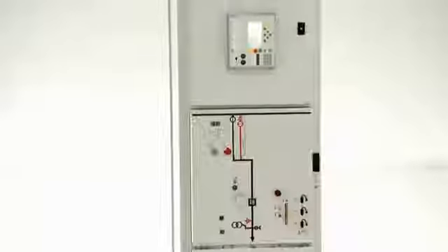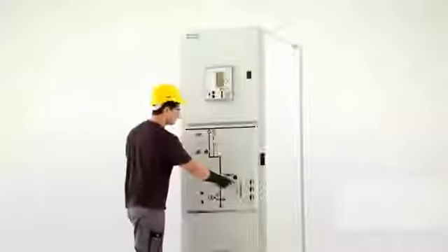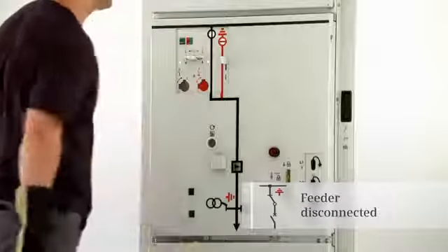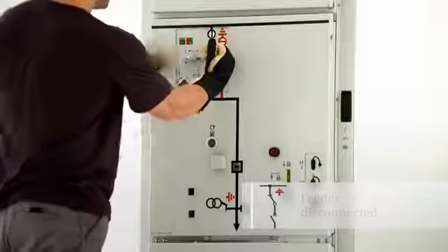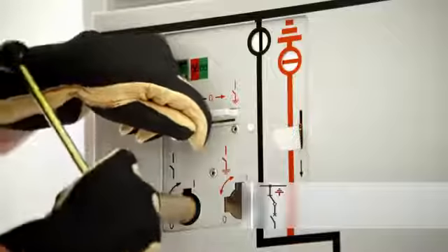So, a choice is made regarding the planned switching operation, choose, which is then completed by closing the circuit breaker, execute. We'd like to show you this principle in more detail, using NX plus C as an example. To disconnect a feeder from the bus bar and to earth it subsequently, the circuit breaker is first switched to the open position. Only after the interrogation lever has been pushed down and the control gate has been pushed to the left can the three-position disconnector be switched to the open position by turning the operating lever counterclockwise.